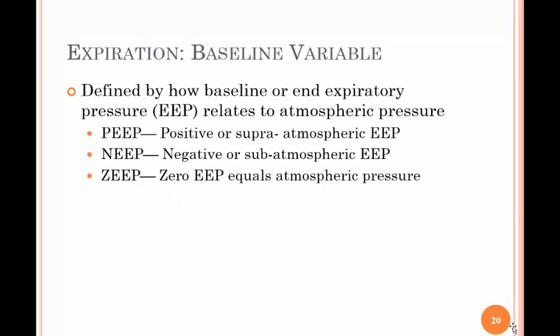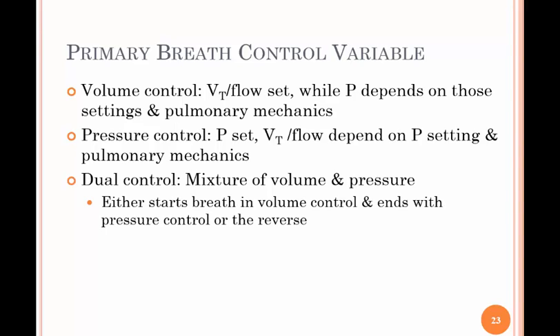The baseline variable defines how the baseline or end-expiratory pressure relates to atmospheric pressure. PEEP is positive end-expiratory pressure. NEEP is negative or subatmospheric end-expiratory pressure. And ZEEP is zero end-expiratory pressure, equal to atmospheric pressure. In volume control, the tidal volume and flow are set while the pressure is dependent on the settings and pulmonary mechanics. In pressure control, the pressure is set and the tidal volume and flow depend on the pressure setting and the pulmonary mechanics — like compliance and resistance.